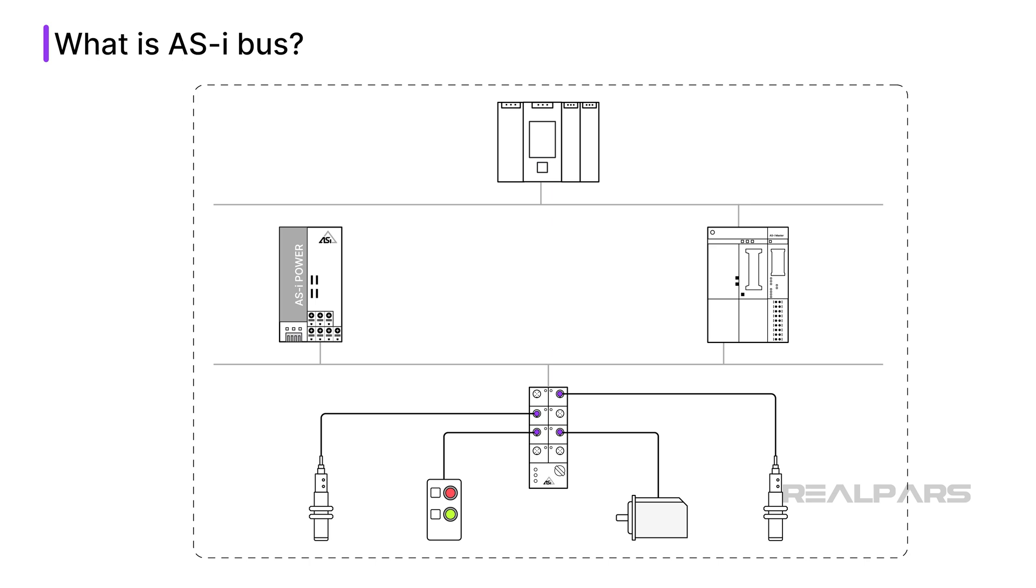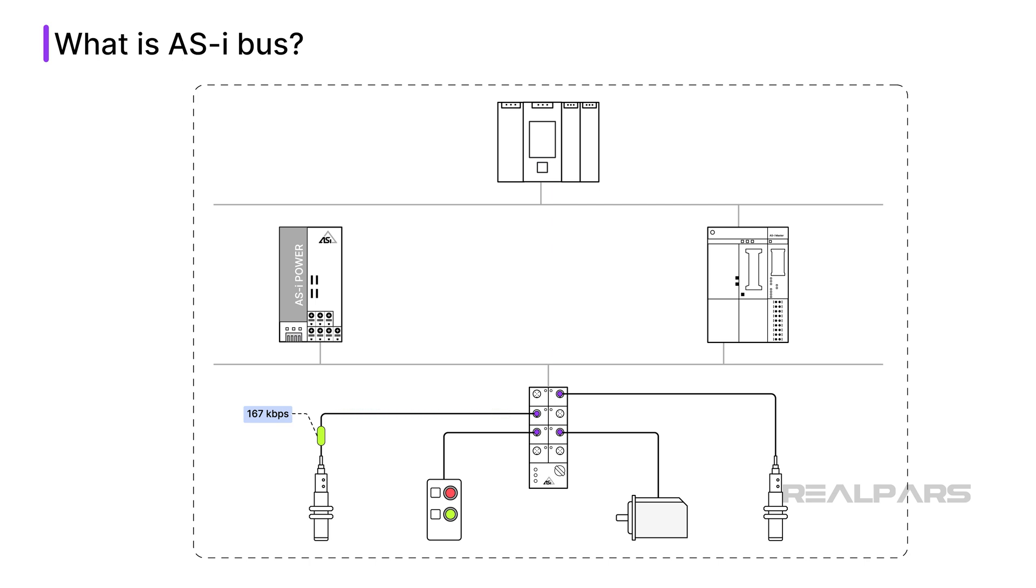AS-i bus is a serial bus, and communication is half-duplex, meaning data can be transmitted only in one direction at a time. The data rate is only 167 kilobits per second, but the simplicity of the network allows a communication turnaround time of only 5 milliseconds.